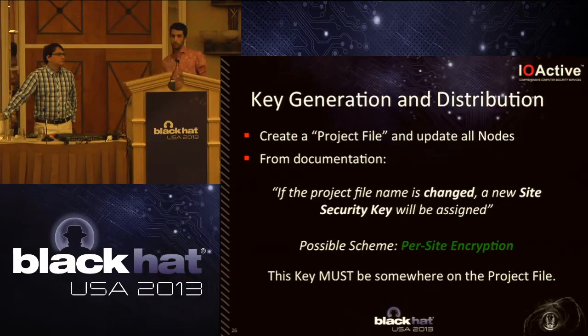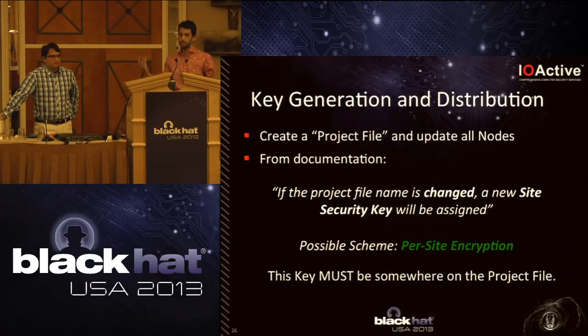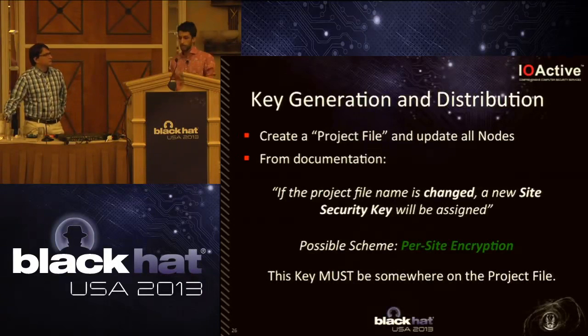So when you create a project file, you set the specific configuration for each of the devices that you are going to interconnect. You set the interval of time that you want, for example, for the transmitter to send the information, because these kinds of transmitters have a battery that lasts, for example, 10 years, and if you raise the interval, you will get more and more time available.